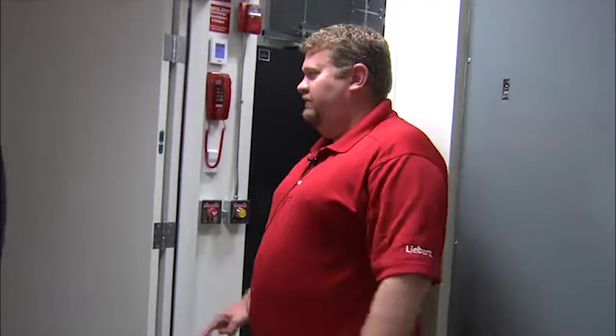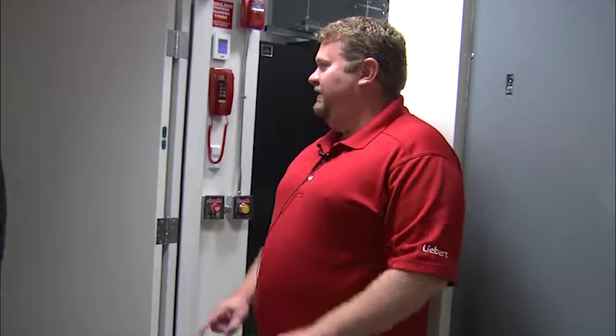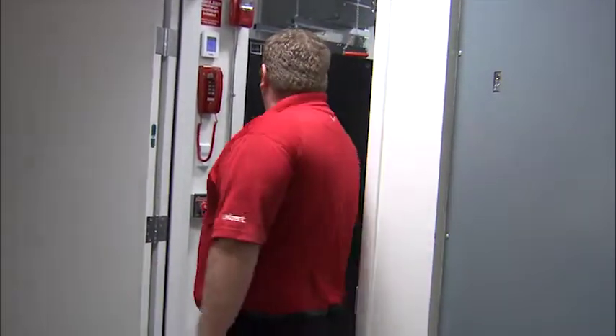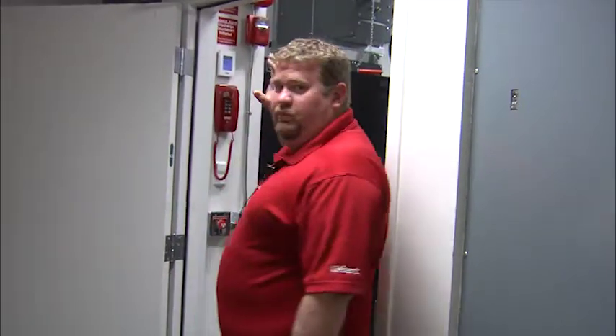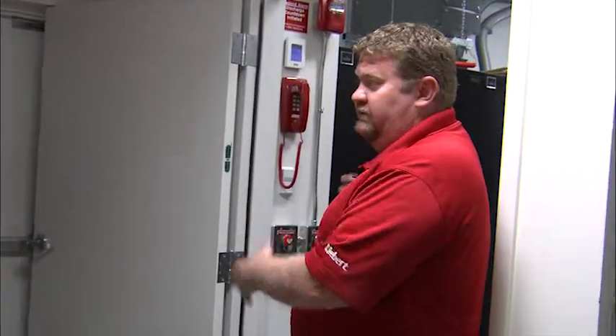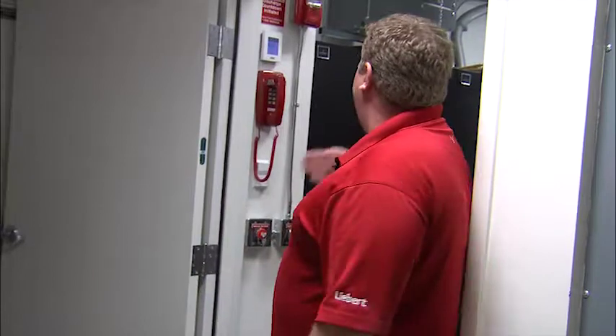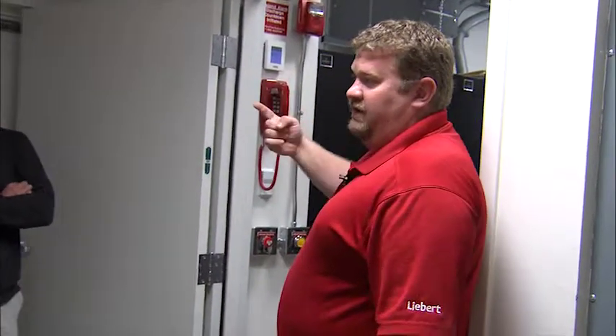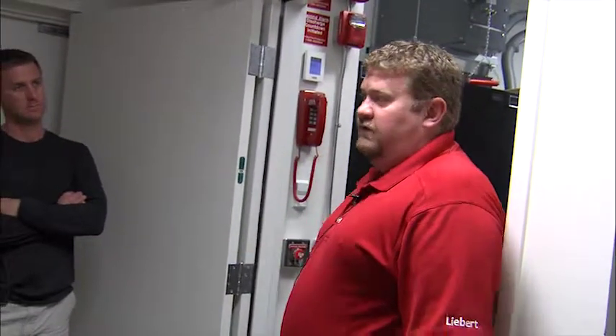Again, what's the most important thing? Site ID and tag. Yep. Now I want to go over the overhead input and output, which is a complete wraparound system. So if they ever had a major malfunction, a bus failure, a fire, something within one of these UPSs, and they have to pull this UPS out and replace the whole thing, what we have the ability to do is go into what we call a wraparound bypass, which wraps around the whole UPS system and still feeds power over to your panel.